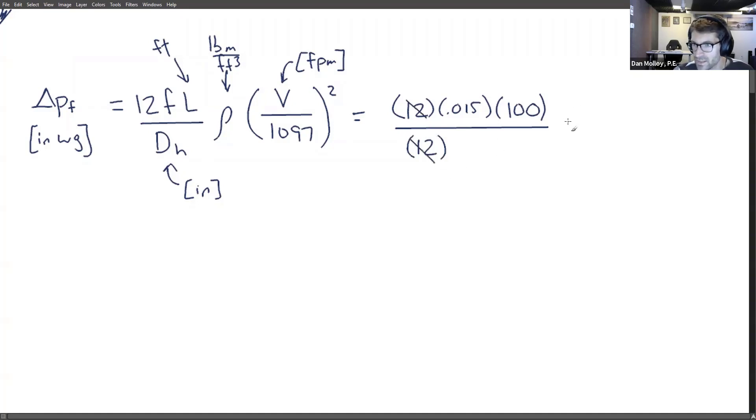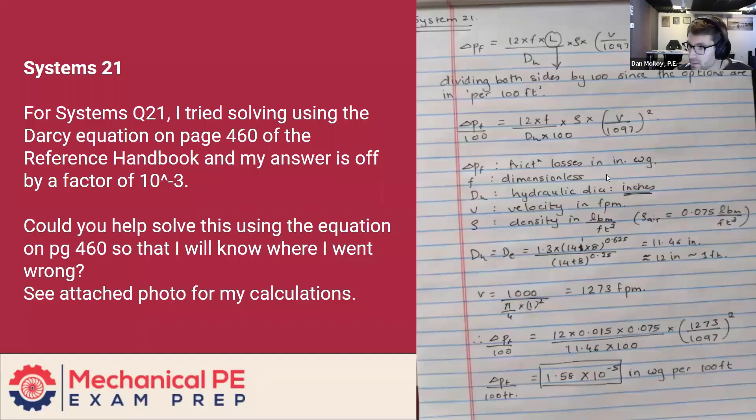Now the density, which for air is typically about 0.075. And I believe you made the same assumption for that as well. And then for the velocity, you would work that out to be 1273 feet per minute. And I agree. And that's divided by 1097. And that quantity has to be squared.